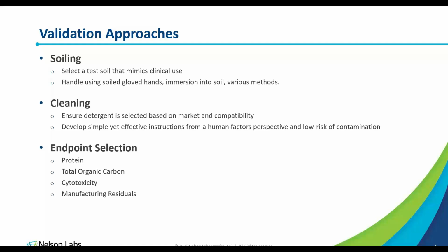And then for endpoint selection, the most common endpoints we see for validations are protein, total organic carbon, and, if the device is patient contacting, cytotoxicity. And then I put manufacturing residuals here as well, even though that is a separate discussion. For 3D printed devices, keep in mind you will need to evaluate manufacturing residuals, such as particulates, THC, and TOC, total organic carbon, which is also something you could do for a manufacturing residual. But these are just the basic approaches we would take for a normal cleaning validation per ST98 and the FDA guidance document for reprocessing.